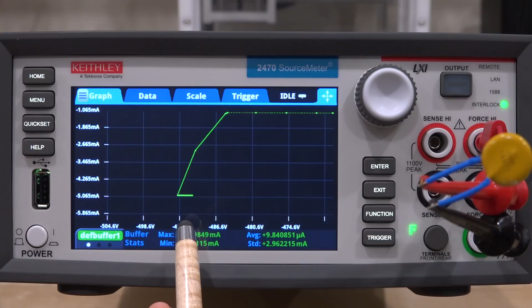Well, that's actually a thermal effect, because as soon as the Varistor has triggered, the instrument is still applying a voltage, but it's already limited to 5 milliamp, and therefore the voltage is clamped to 492 volts. At the same time, the device is warming up, which means the voltage across the Varistor is changing as a function of time now, because it's getting warmer, and therefore the voltage is dropping. So you can see this really subtle behavior of this Varistor by looking at it this way.